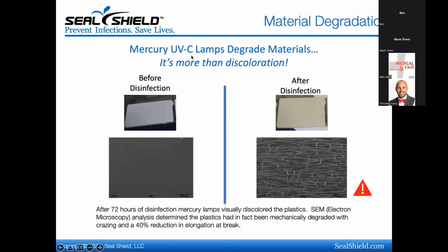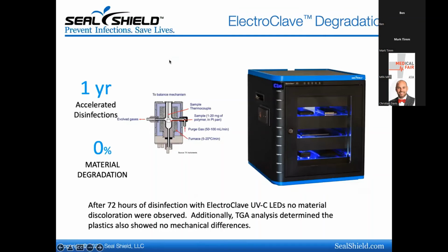So a mercury-based UVC system turns plastics into a surface that can no longer, after 72 hours, continue to be disinfected with UVC. Why? All the pathogens and microorganisms fall into all of these cracks that you see in the SEM image. This is the same magnification before and after exposure. And once the organisms are in these crevices, they can no longer be disinfected. The electroclave is unique in that it uses a UVC LED system. It does not use a mercury-based system, so therefore we have zero material degradation in our cabinet. We have proved through lengthy studies that we do not have any material degradation in the electroclave. We've done that through studies to include TGA analysis, where we've inspected polymers through the TGA process to ensure that there has been no molecular change to that polymer over, again, that same 72 hours of disinfection.